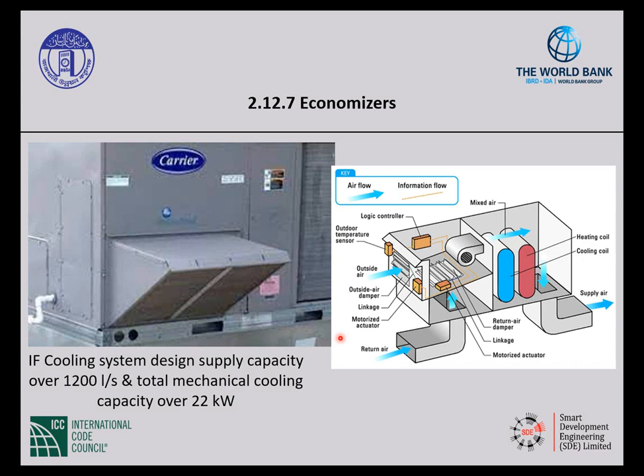So there are some exceptions. Again, it's only required on those systems that have over 1,200 liters per second design supply capacity and total cooling capacity over 6.3 tons. And then if you're in a hot and dry or a warm, humid climate, you're exempted out of these economizer requirements. In a hot and dry climate, the air might be too dry, but the hot means we're probably not going to drop down to a level where the outside temperature is cooler than what we want anyway, so we're not going to worry about jumping through the hoops on those. Humid climates, we probably don't want all that humidity in the building anyway.